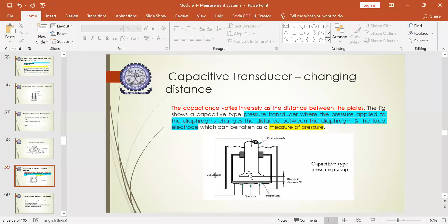The gap or clearance between the electrode and the diaphragm varies due to the applied pressure. This variation in the distance results in identifying the amount of pressure change. It can help in measuring pressure due to variation in the gap between the electrode and the diaphragm. This is how pressure is measured using a capacitive transducer by change in distance — the distance gets automatically changed due to the applied pressure, and from that variation in distance the pressure change can be calculated.